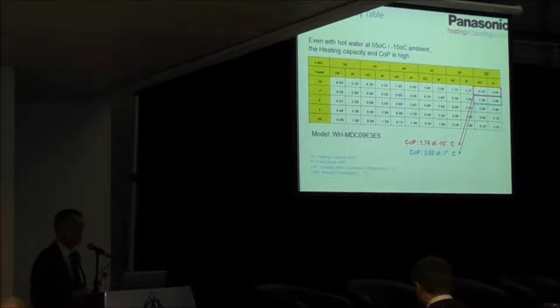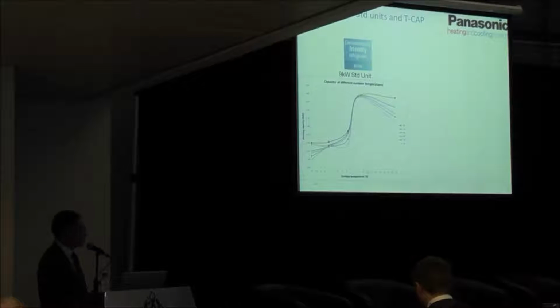And even when we go to higher temperatures, for example, water up to 55 degrees C, the COPs will still be reasonable. So I spoke earlier about three different types of units: the standard high connectivity type, the total capacity type, and high temperature. So the units I tested, I don't know how well you can see that, but here's the ambient temperature down here, going from plus 25 to minus 15. Here's the heat output going from 4.5 up to 9.5, and here's different water temperatures.